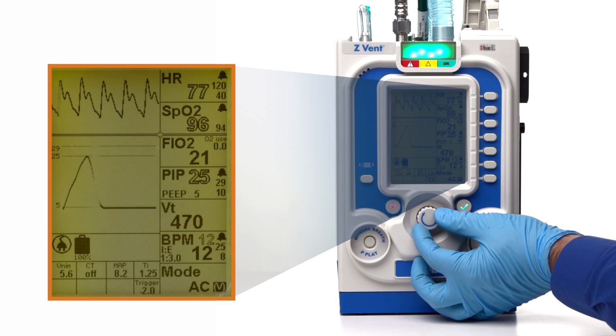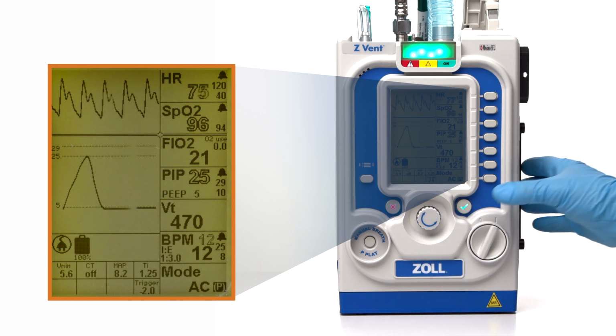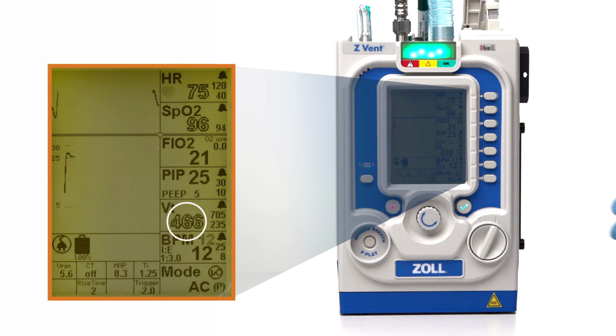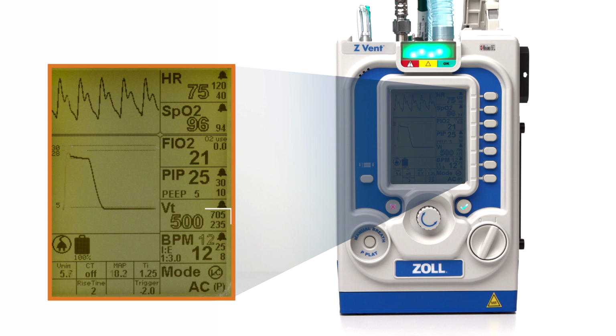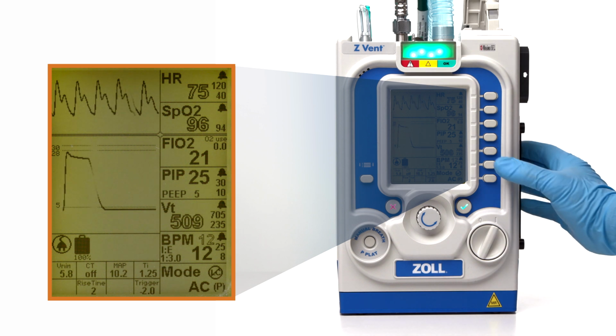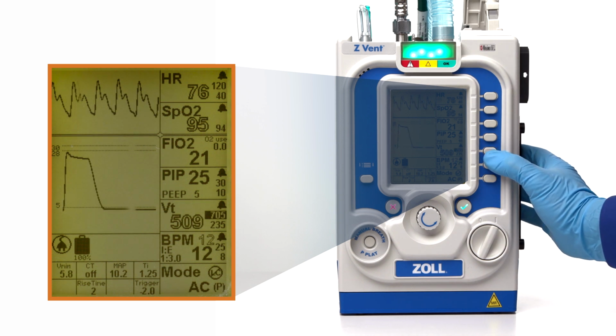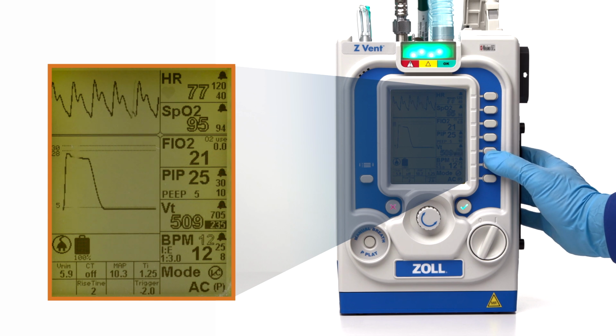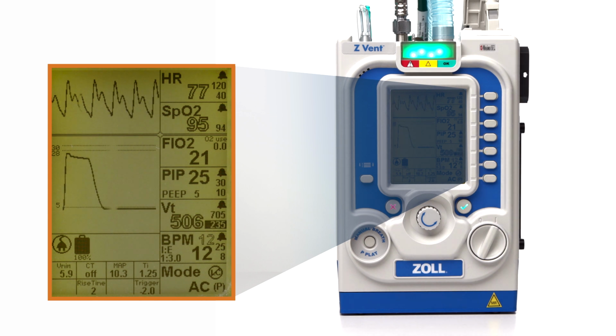When operating in pressure-targeted breathing mode, the tidal volume is a calculated value and will display as an outlined number that cannot be changed. However, the user now has the option to change the high tidal volume and low tidal volume alarm ranges. Press the parameter button once to change the high tidal volume alarm and twice to change the low tidal volume alarm.